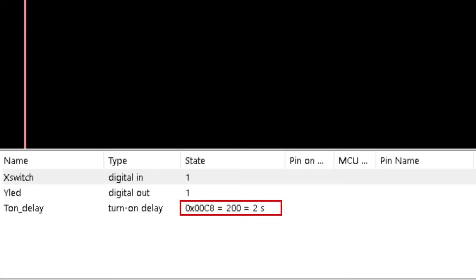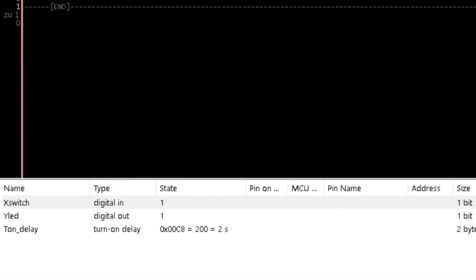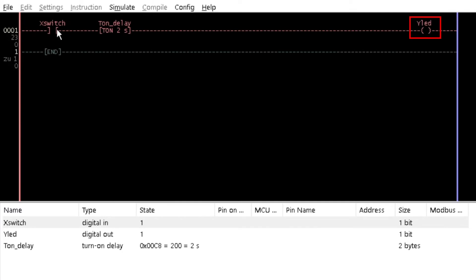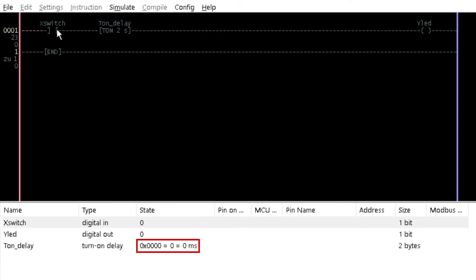Thus, the final value of T on delay is 0x00C8 in hexadecimal, which is equal to 200 — instead of 2000 milliseconds — equal to 2 seconds. When the time interval elapses, Yled is then activated. Double click on X switch again and observe that Yled is immediately deactivated and T on delay state is reset to 0.